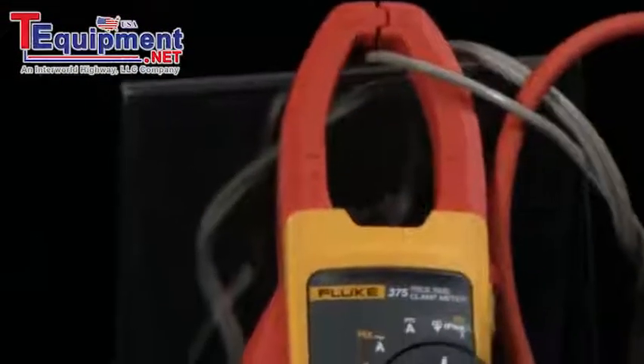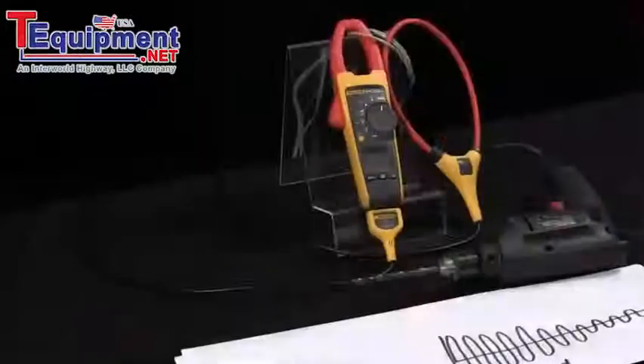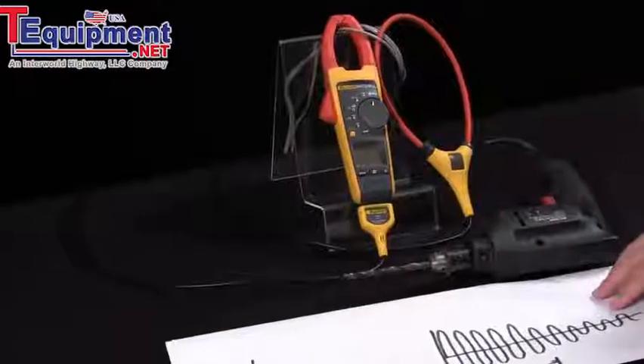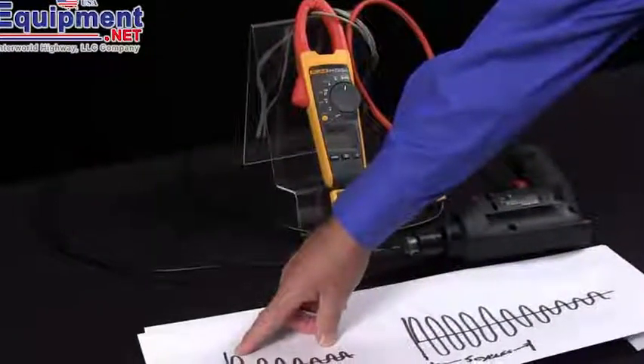To use inrush with iFlex, we simply turn it to the iFlex mode instead of the normal current mode, hit the inrush mode and now we can capture inrush. Fluke has a unique design in that we don't capture the first peak that we see with the amps.